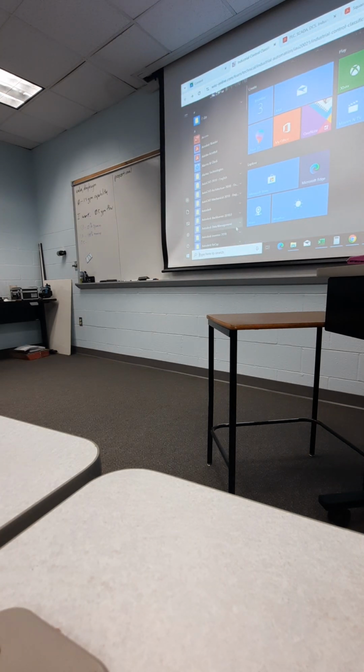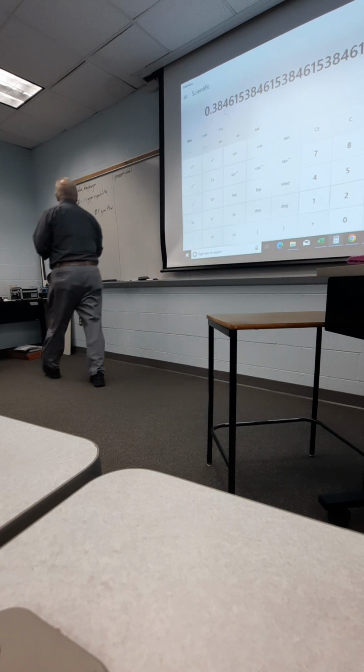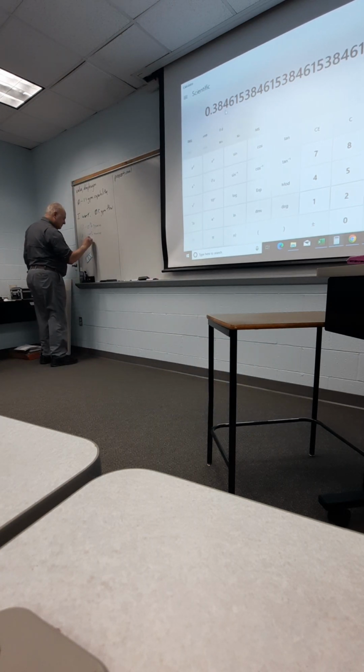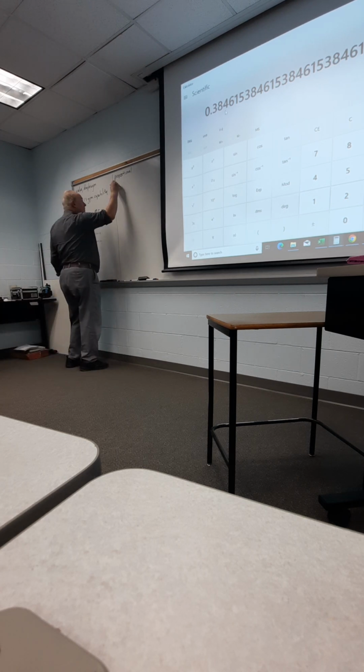And of course, to save you time, I'll go into a calculator. 0.5 divided by 1.3 equals about 38%. So if this is a proportional system, how do we want to set our valve? Well, 38% valve opening.